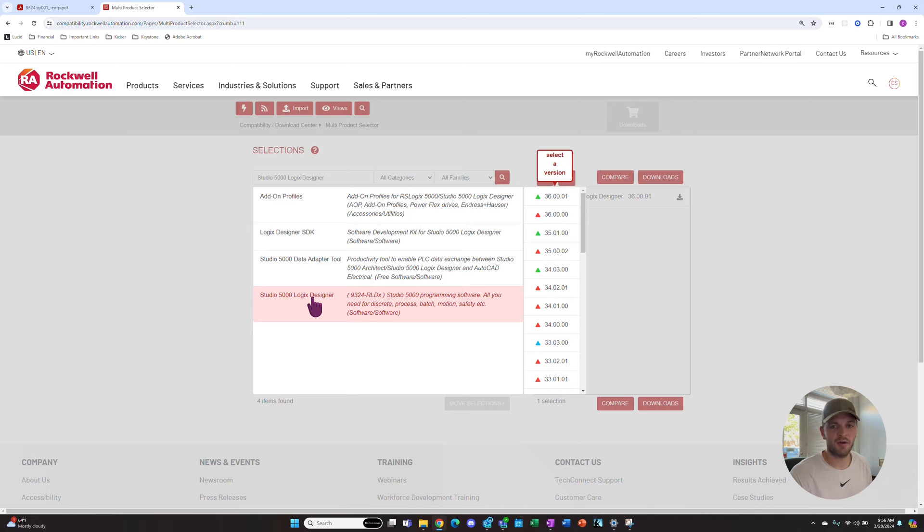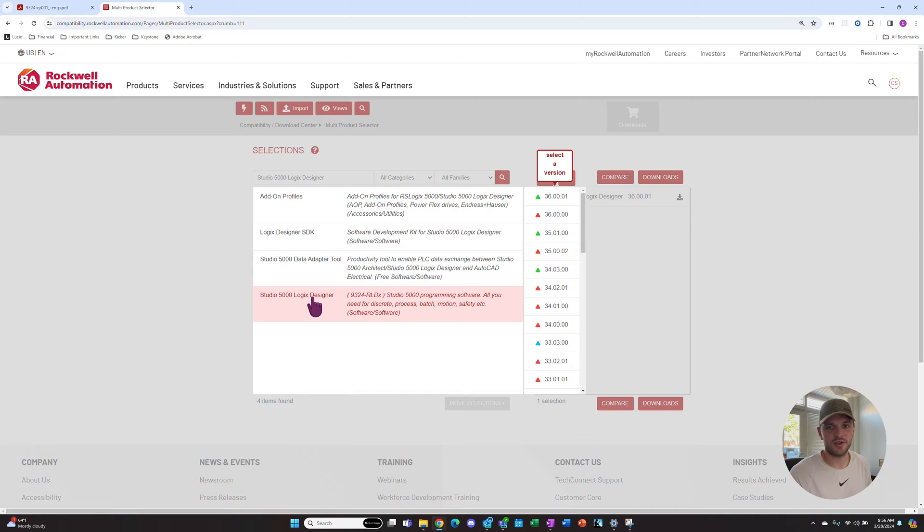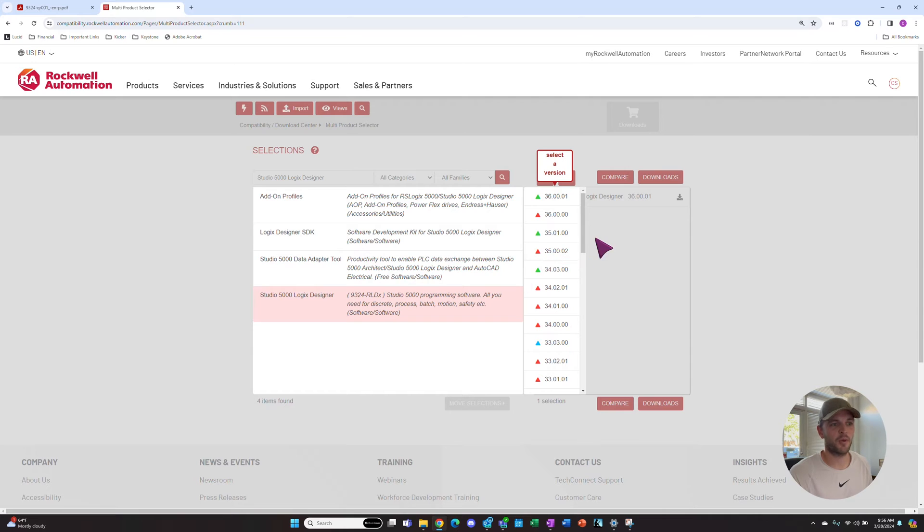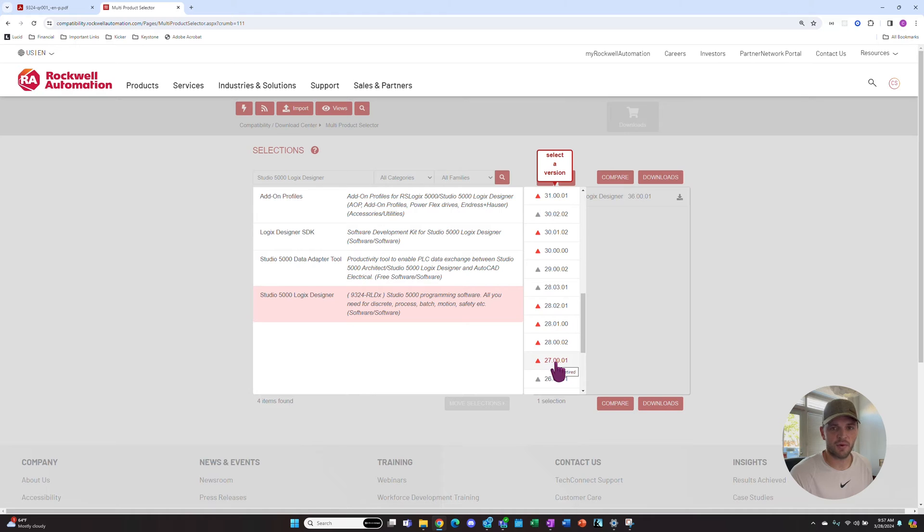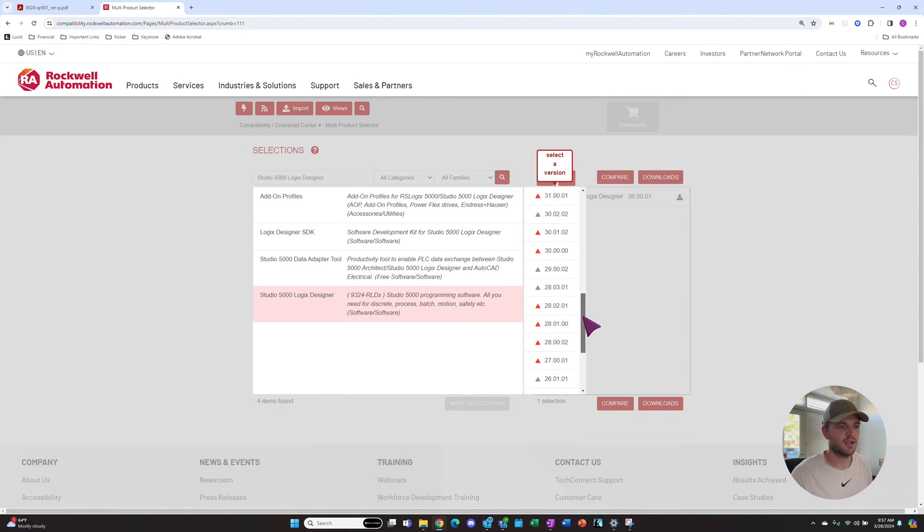Now it wants us to select a version. The version number of the software must match your firmware revision number in your PLC. So if your PLC has a firmware revision number of 27, then your software must also have version 27 so you can program that PLC.